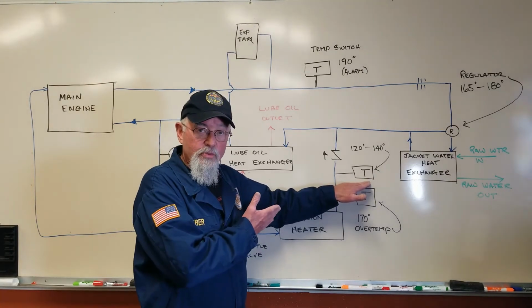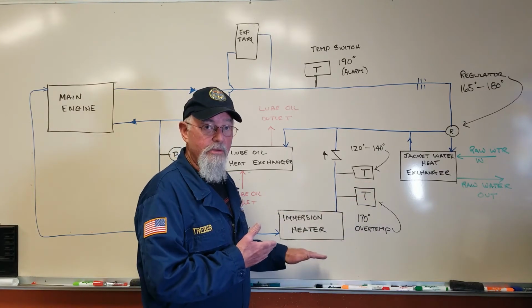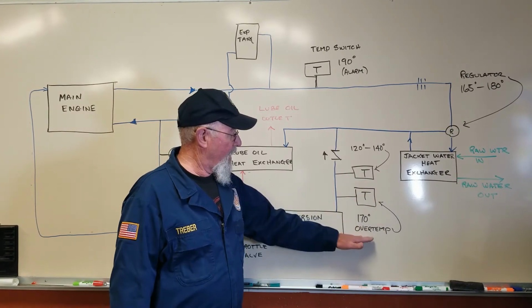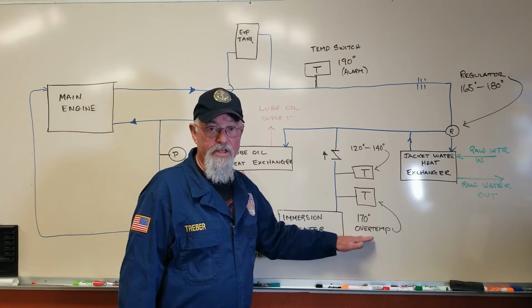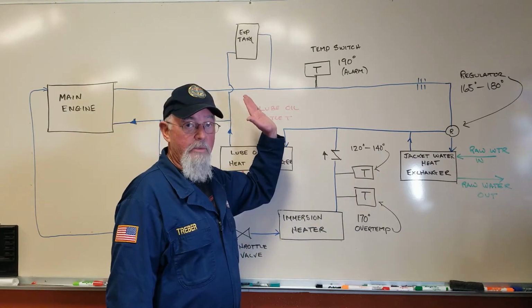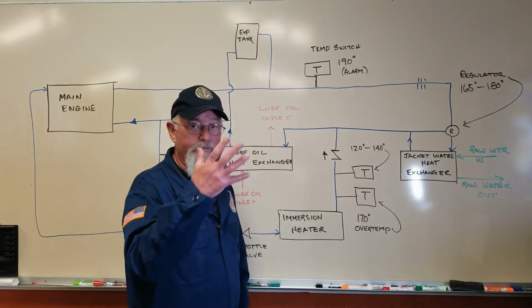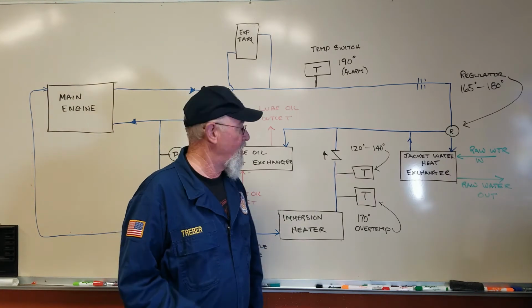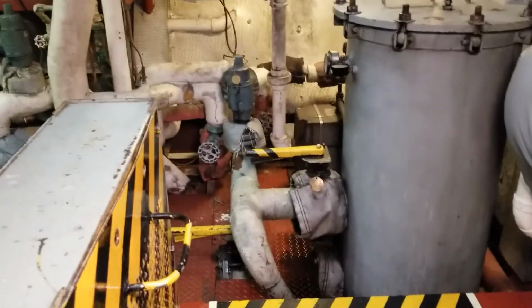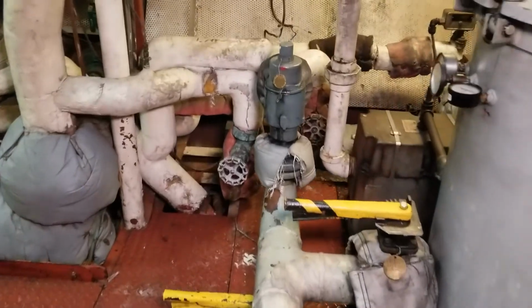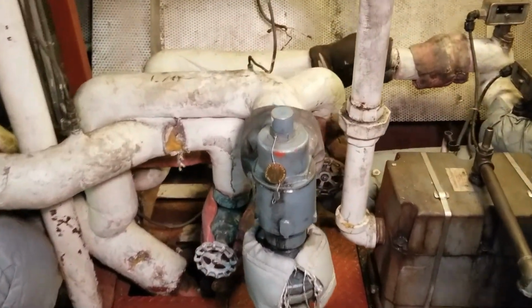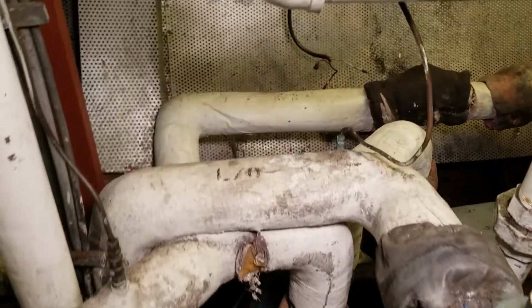Now, if this temperature switch fails and doesn't de-energize the immersion heater, then when that temperature reaches 170 degrees, game over. It shuts it down. So we're going to have some human intervention here and do something about it. So we'll go over here and take a look at the immersion heater pump.